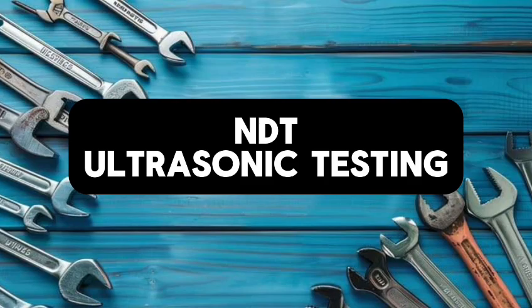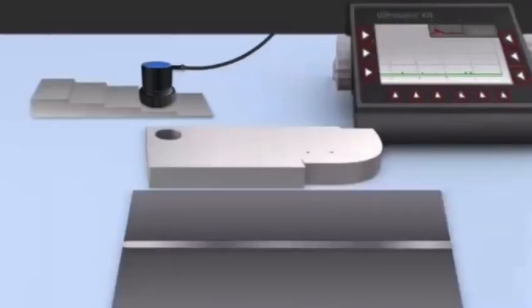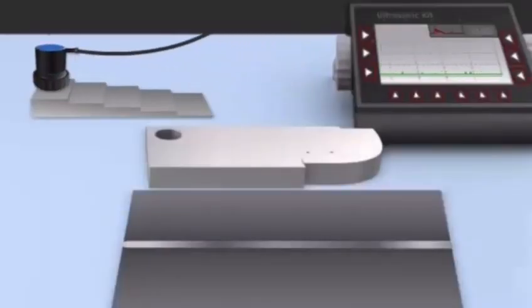Working principle of ultrasonic testing. Ultrasonic testing uses a beam of ultrasonic waves produced by a transducer. These waves are passed into the part to be tested. The setup has a transducer unit with a display for output, a probe to check the object, and a standard gauge block to calibrate the instrument. The principle and operation are explained here.